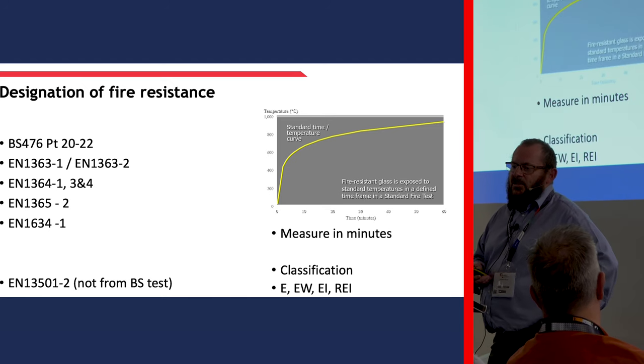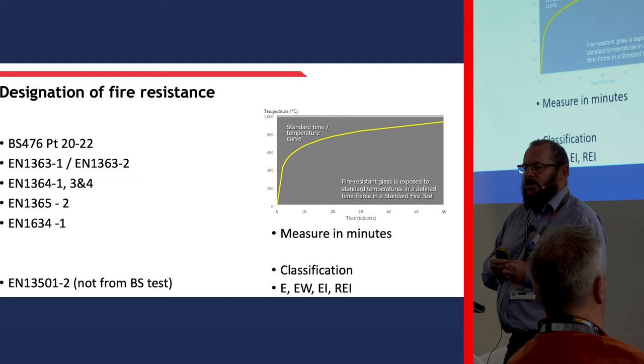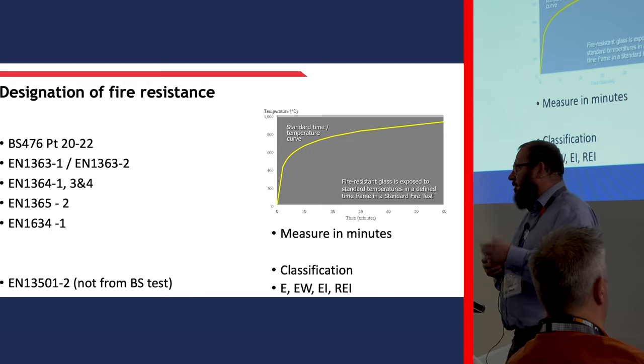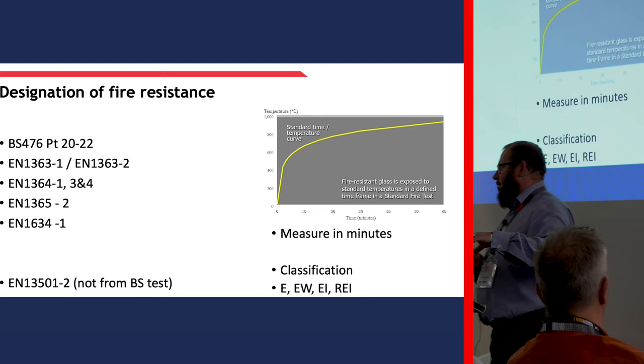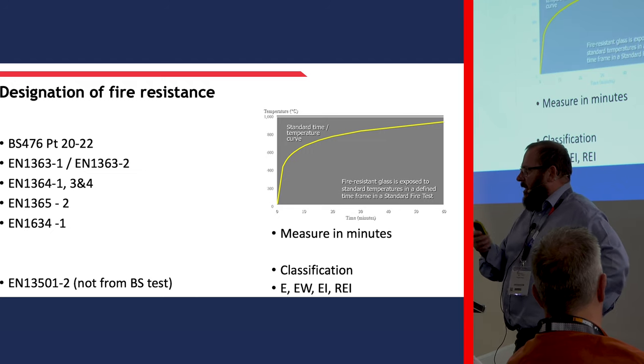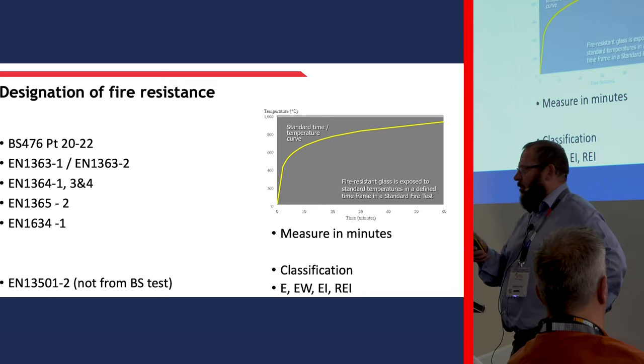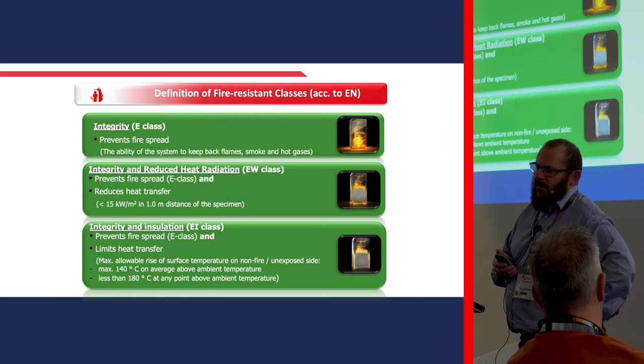To achieve classification to fire resistance, we need to conduct tests to these standards. The time temperature curve is generally the same between the British standard and the European standards. Depending on which test you carry out - doors, screens or floors - these are the tests that apply. You then have to get a classification to EN 13501 Part 2. It's important to note that you cannot get that European classification from a British standard test. From a European test, you get a classification of E, EW, EI, or REI if you're using loaded floors. Where E is integrity, EW is integrity with radiated heat protection, and EI is integrity and insulation.